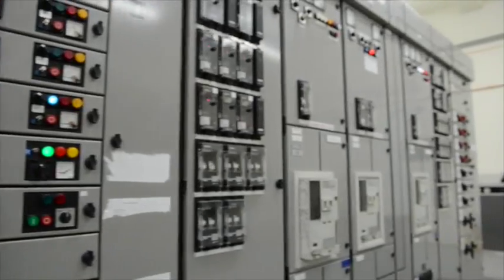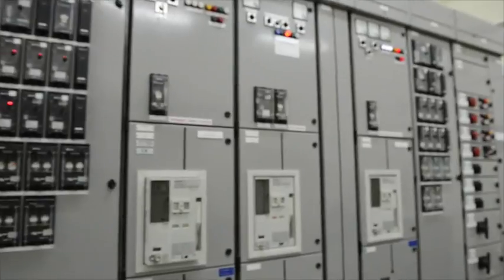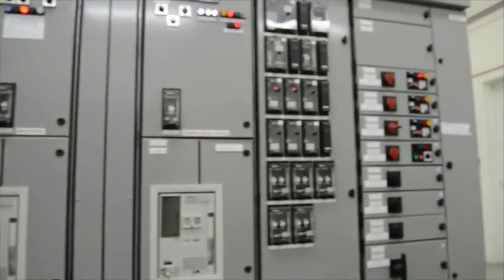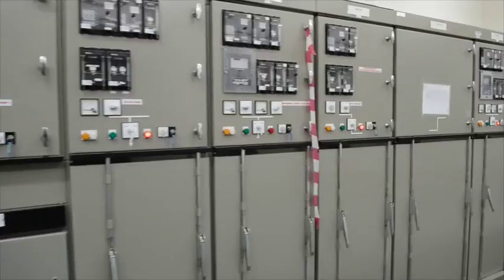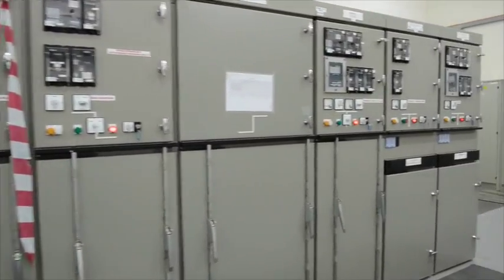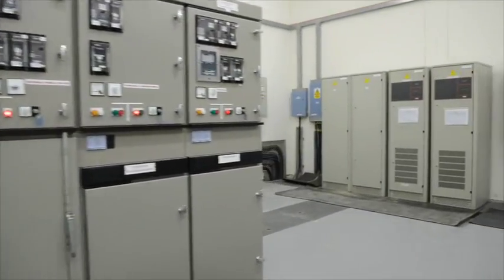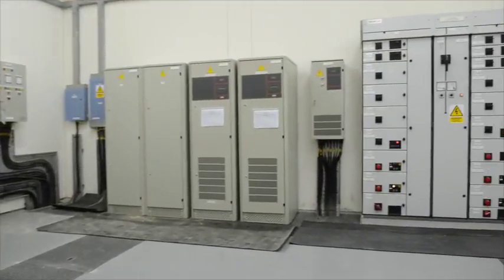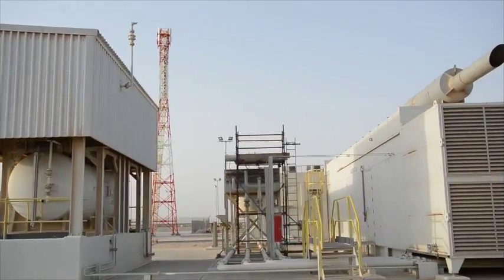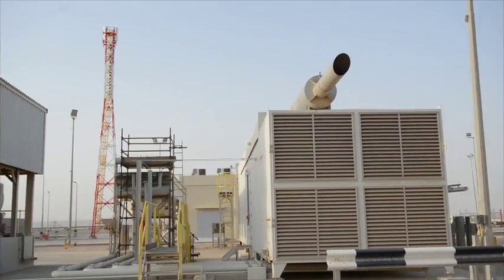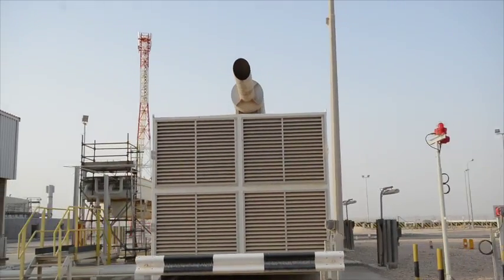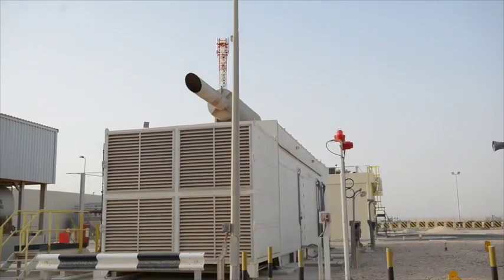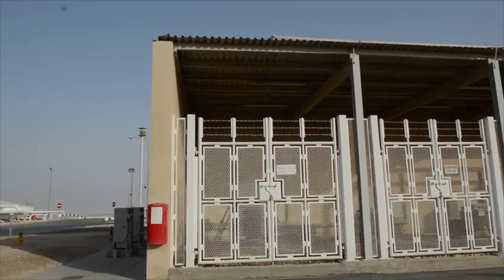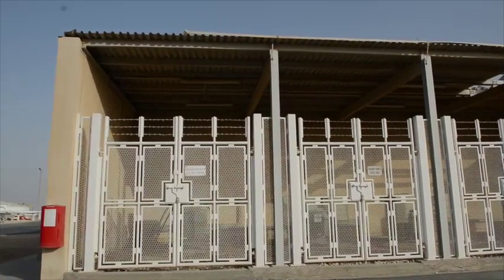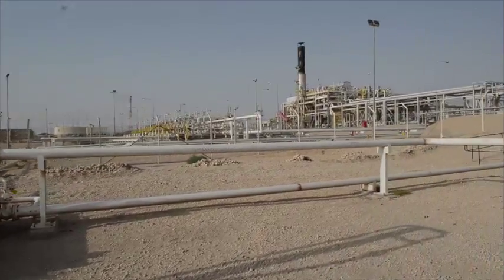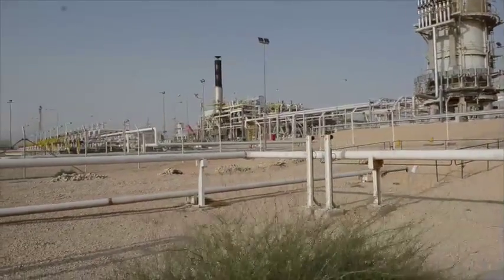The degassing station is powered by 33 kilovolt overhead lines to three separate substations. At each substation, the 33 kilovolt supply feeds into two transformers to step down the voltage to 3.3 kilovolts. The first substation supplies power to the gas compression and gas lift facilities. A 2.2 megawatt standby diesel generator starts up automatically on failure of this power supply. The second substation supplies the tank vapor blower, while the third substation supplies the main oil line pump.